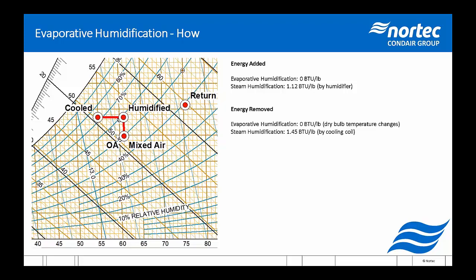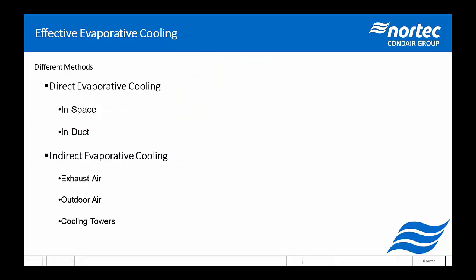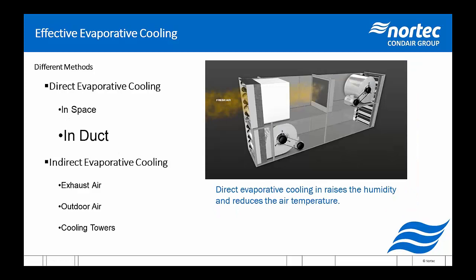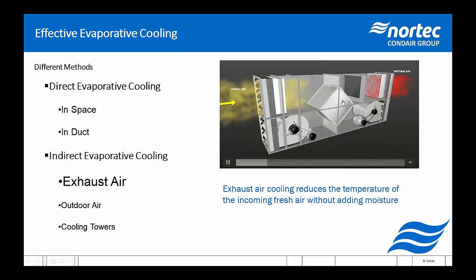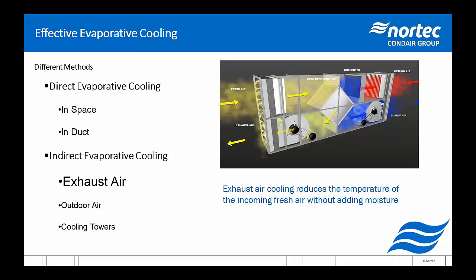So I've got a question here about the DL specifically. How is it controlled to utilize the most energy savings in a heat wheel custom air handler application? If we're looking at the DL, it works the same as any of these other situations in which we have in-duct cooling. So we would be looking at an in-duct system like this. However, in this case, in the question, we're looking at a heat wheel as well. So rather than a sensible heat exchanger, we'll be looking at an enthalpy wheel that transfers both humidity and energy out of the system. So when we're looking at a DL, in this case, we would apply it for direct cooling and humidification.